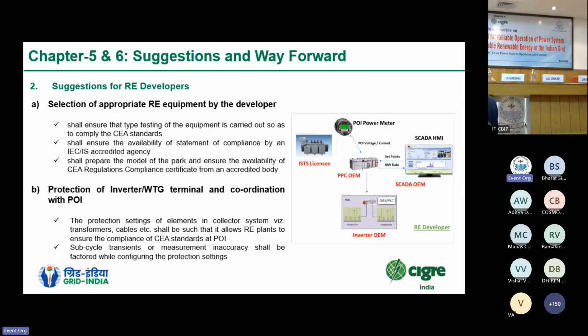Again, a suggestion for RE developers: they shall ensure that type testing of equipment is carried out so as to comply with the CEA standards. Type testing is a very important aspect, and it should be carried out by accredited agencies so that the equipment, in its lifetime, is able to display the desired performance. Any quality compromise would be checked at the pre-commissioning stage itself. So equipment should be type tested, and the availability of a statement of compliance by an accredited agency should be ensured. These things at the pre-commissioning stage, like statement of compliance and monitoring, can help us in avoiding issues during the operation phase of the plant.